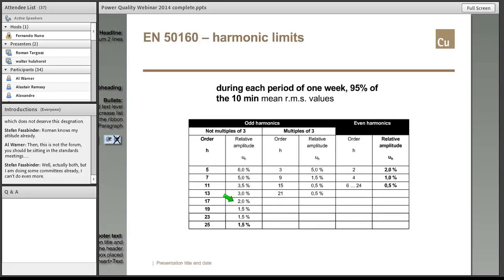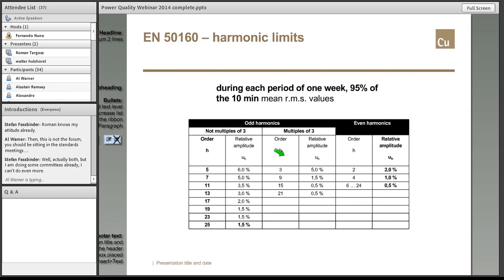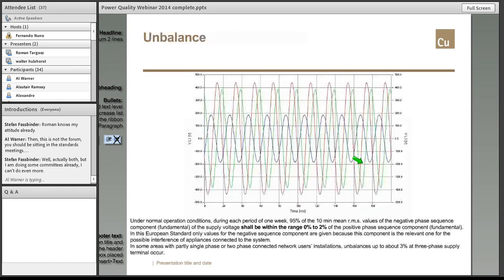I will speed up. Now we've got the same: during each period of 1 week, 95% of each of 10 minutes mean RMS values. So we've got positive and then negative sequence harmonics. We've got zero sequence harmonics, and we've got even harmonics levels in EN 50160. Then we've got unbalance, and for 95% of 10 minutes RMS, the ratio of negative to positive sequence should be up to 2%. In some exceptional cases, it should be up to 3%.